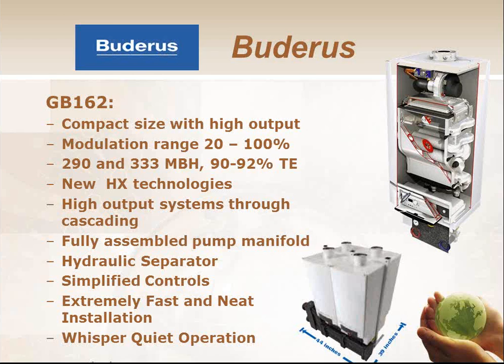And by the way, when we talk about these MBHs and BTUs, that's input on these boilers. So when we come back to that right sizing thing, sometimes you take out a 100,000 BTU boiler and you want to put 100,000 in condensing. Well, the 100,000 old one that was 80% efficient really only had 80,000 output. Now you put in 95%, I got 95,000 output. So I've inadvertently oversized it if I pick the same size condensing boiler as non-condensing when I change it out. So all the more reason to right size it and round down a little bit there.